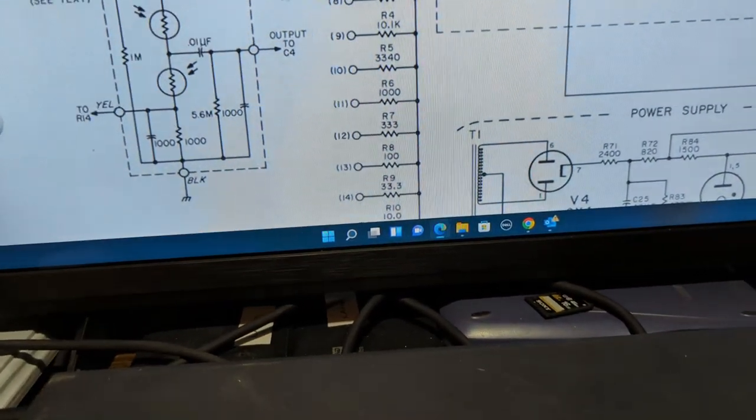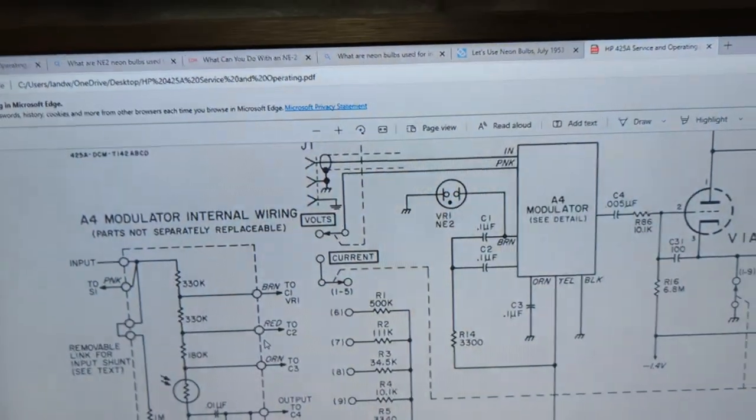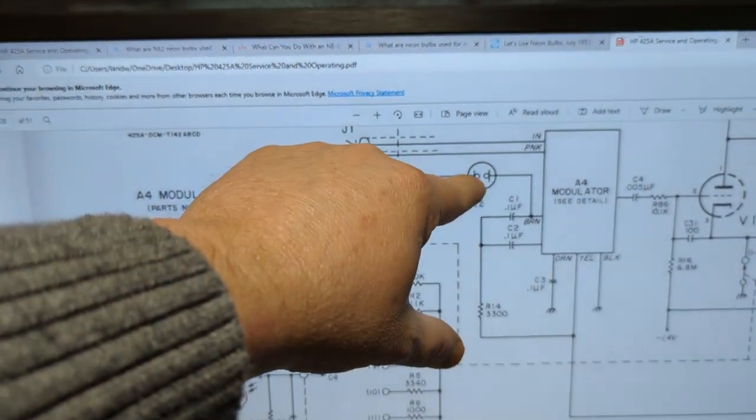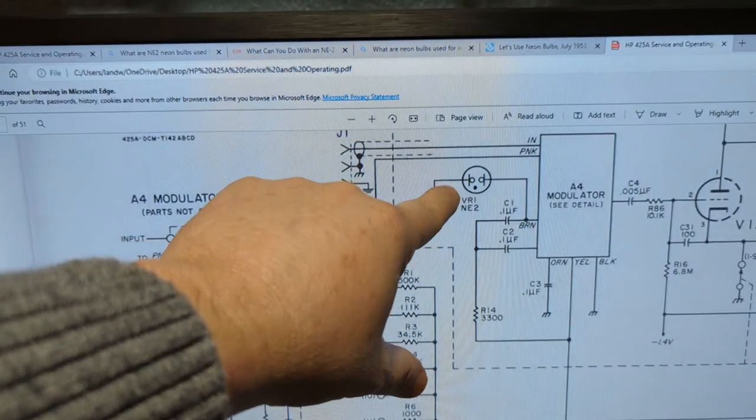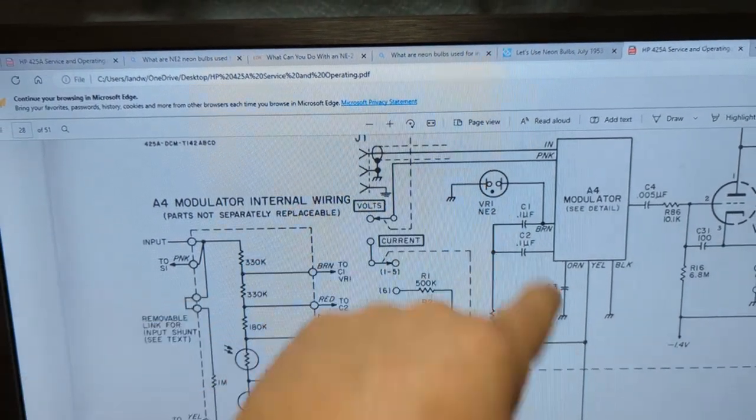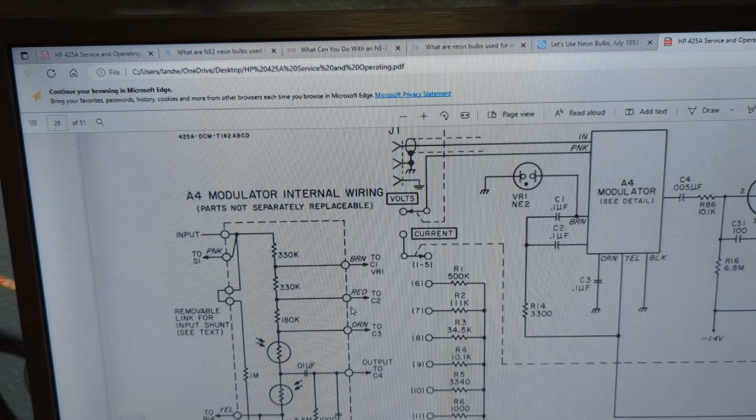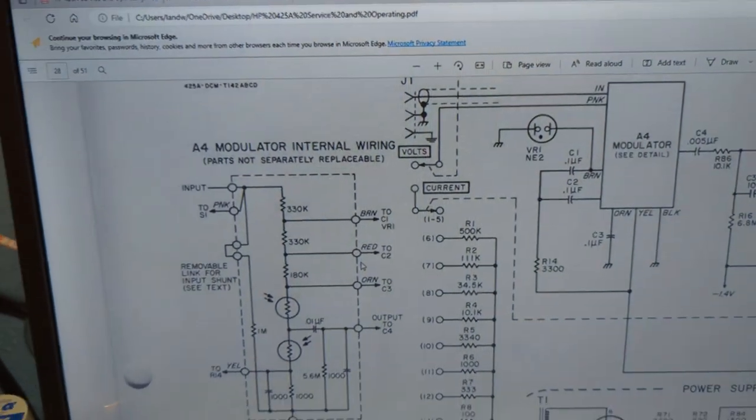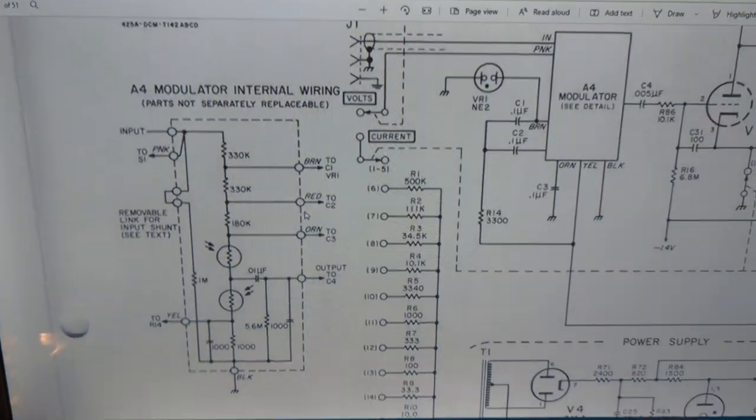And based off of their on and offness, your output is going to be determined, okay. And that output's going to go over here to C4, which is your output right here. This is what's going to be amplified at the end here, at your first stage of amplification. So that's what's happened in the modulator - it's basically taking the DC signal that's coming in here, modulating it with this signal that you're creating with this chopper, and amplifying it on the other end in a nutshell. There's your regulator. Right up here, there's that neon bulb. See, it's just connected to ground, so basically it's just being used as a protection device. That's it.